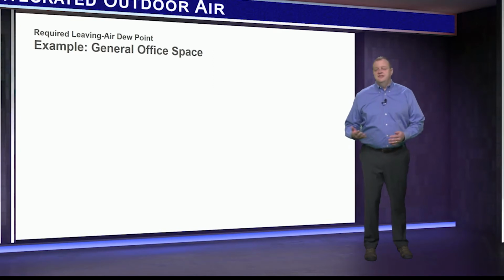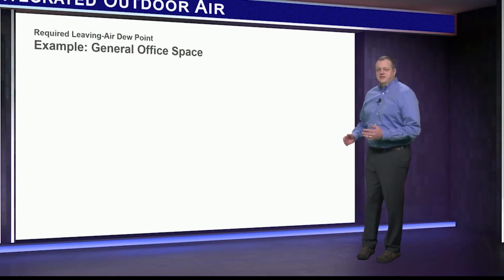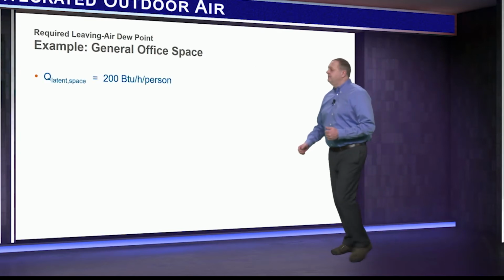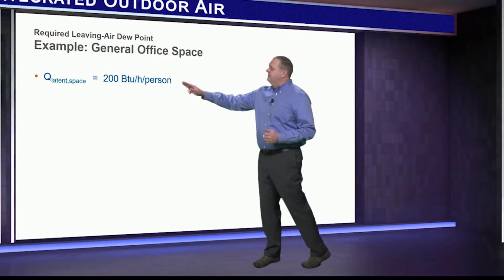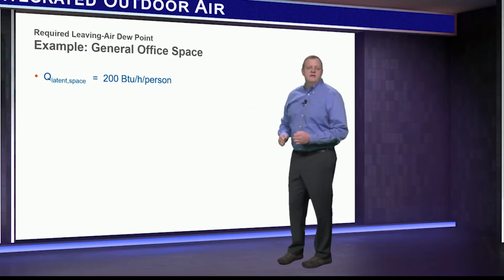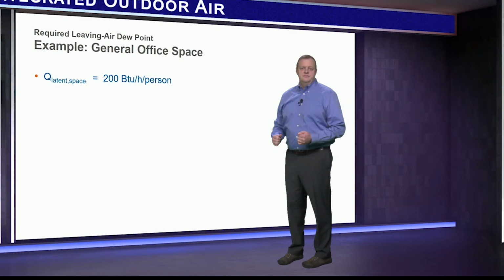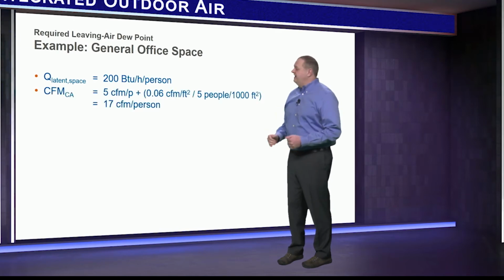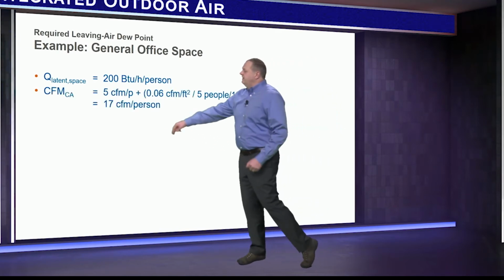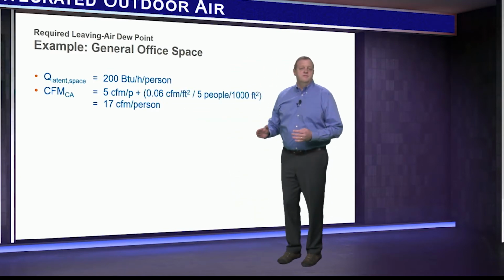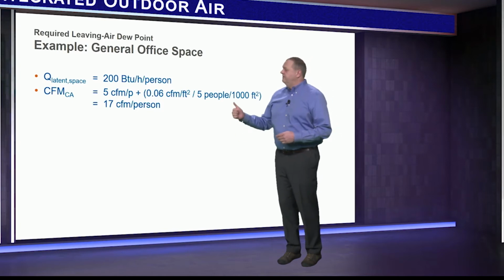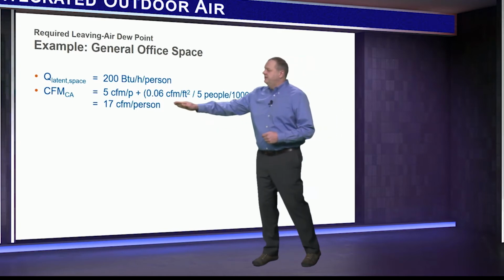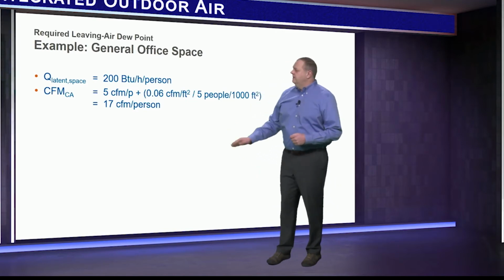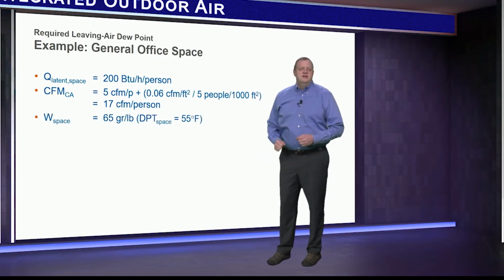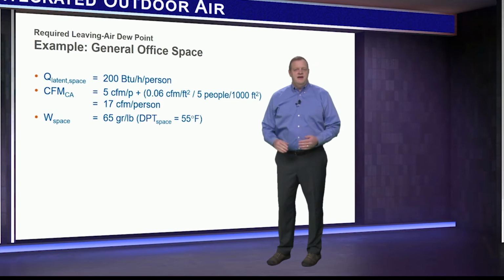As an example, let's consider a typical office space. Assuming the only latent load in the space is due to people, the ASHRAE handbook suggests a latent load of 200 BTUs per hour for each person doing active office work. Then, ASHRAE standard 62.1 requires 5 CFM per person plus 0.06 CFM per square foot for an office space. Using the default occupant density, this equates to 17 CFM per person. Finally, a 55-degree dew point in the space equates to a humidity ratio of 65 grains per pound.